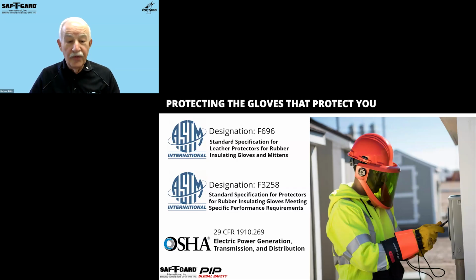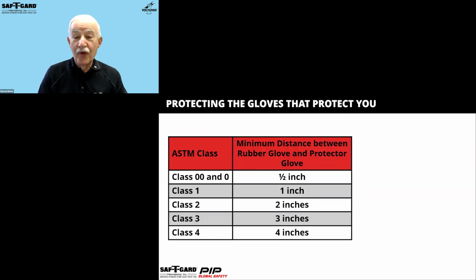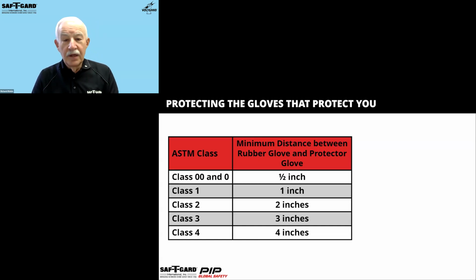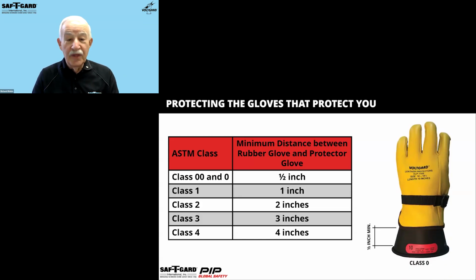These are the things that are important that are going to save your life and your worker's life. Now, keep in mind there is a tracking and flashover risk, which increases as the voltage potential increases. Since the materials in the protector gloves have no dielectric properties, the rubber protects from the electricity. Those materials may occasionally absorb moisture or possibly track electricity. So it is important to maintain a gap between the protector glove and the wearer's body parts, the hand and arm. To do that, the protector glove must be shorter than the rubber glove, so there is exposed rubber as a line of defense against tracking and flashover.